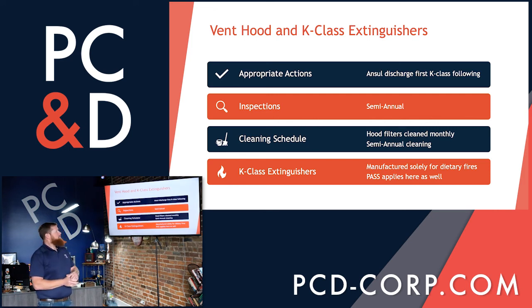The appropriate actions, as mentioned beforehand, is always discharge your Ansul first. A lot of times what happens is people come across a grease fire and they say, well, it's minute, I can take care of that myself with a K-class. It ends up being a little more than they can handle, and they still end up fleeing from the area and sometimes even forgetting to pull the Ansul chain. So always start with Ansul.